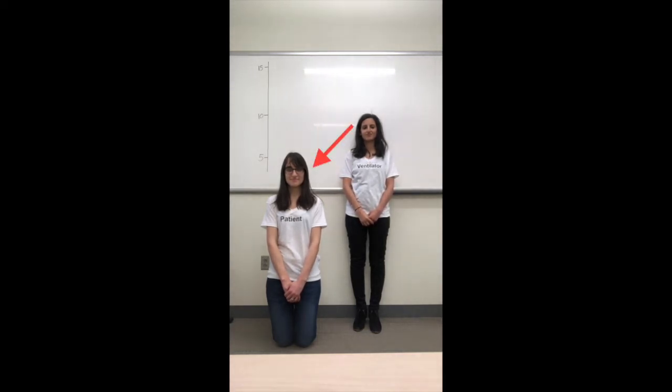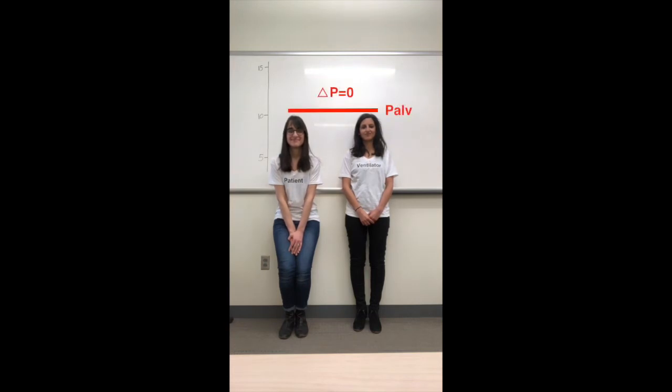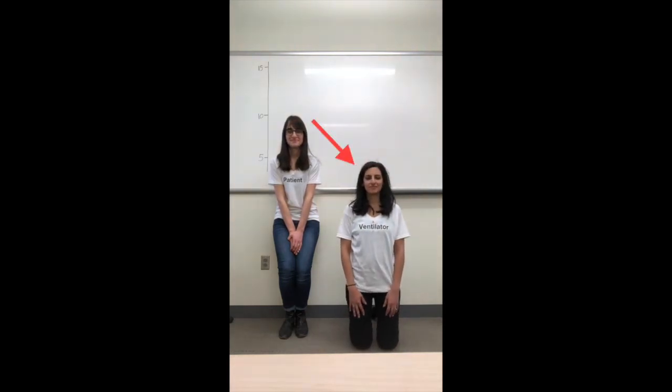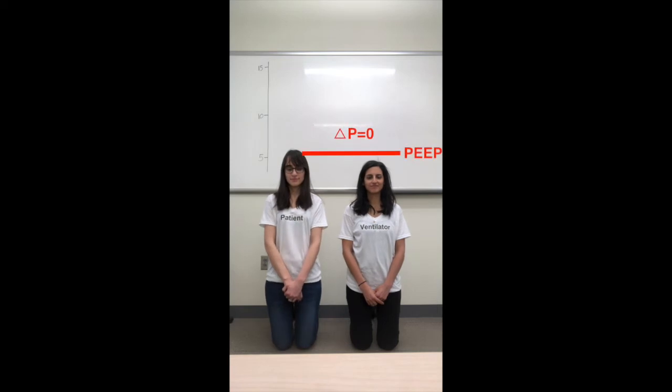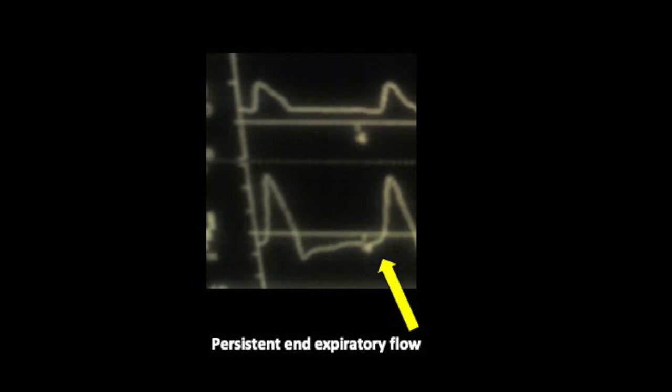In a typical passive patient without auto-PEEP, during inspiration, the pressure rises in the ventilator — I'm going to stand up to demonstrate that there is now high pressure in the ventilator. There is a delta P, or pressure differential, therefore flow is going to go into the patient and my friend is going to stand up as tall as me. Now that we are at the same pressure at the end of inspiration, there is no more flow and inspiration has ended. Then during exhalation, I as the ventilator go back down to PEEP, and she also kneels back down to the same level, so we are both back to PEEP at the end of exhalation. Because our delta P is zero, there is no flow at the end of expiration — in contrast to a situation with auto-PEEP, where there would remain a delta P manifest as persistent end-expiratory flow visible in the ventilator waveforms.